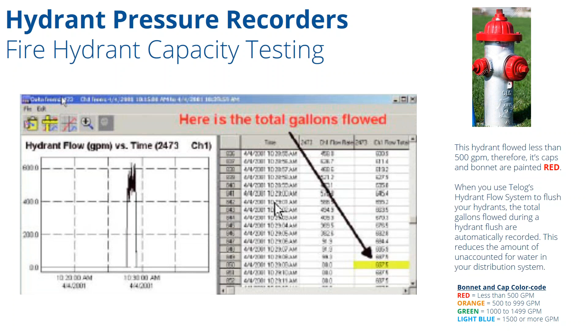Instead of just leaving a hydrant open for an hour, you can actually see live results. Really, all you need to do is flow 1,000 gallons, not leave it open for an hour. Using a measuring device like our hydrant pressure recorder, you can tell exactly when to shut the fire hydrant off after 1,000 gallons have escaped. This helps with your unaccounted for water. Leak detection is a big thing for us, but non-revenue water and unaccounted for water is really big with Trimble Water, and this application helps with that, since flowing and flushing your hydrants is a yearly activity.